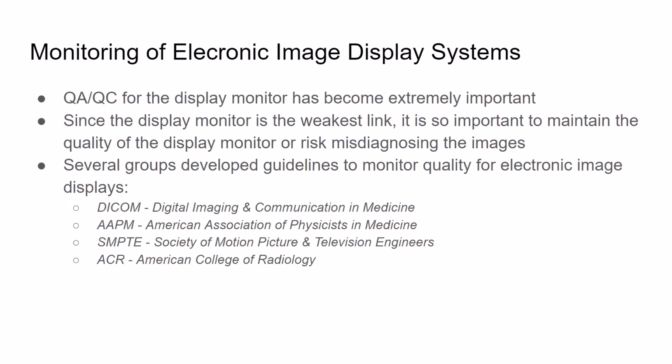We also need to be monitoring the display systems. We have QA and QC for the display monitor, which has become extremely important since the radiologists are reading from these. Because the display monitor is the weakest link, we need this system in place to maintain quality to prevent misdiagnosis of images.